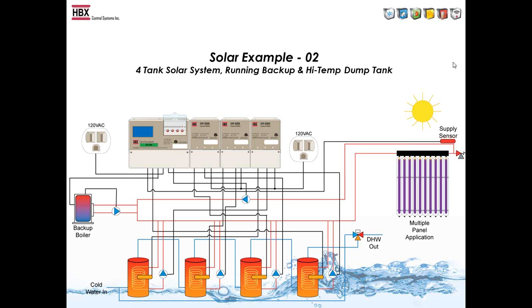So in this case, we are taking the heat from the panels or tubes, and we are choosing which tank it should go into based on the temperature in the tank. Plus, it will keep everything warm if you want the backup on there as well. It can have a dump contact on the control also.